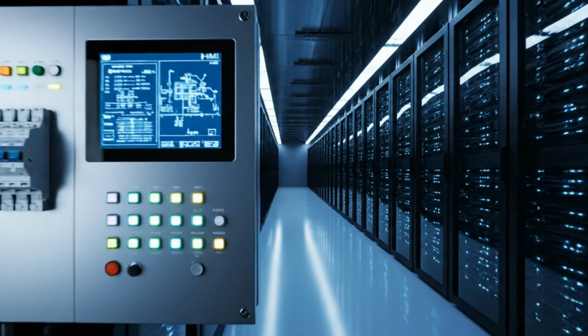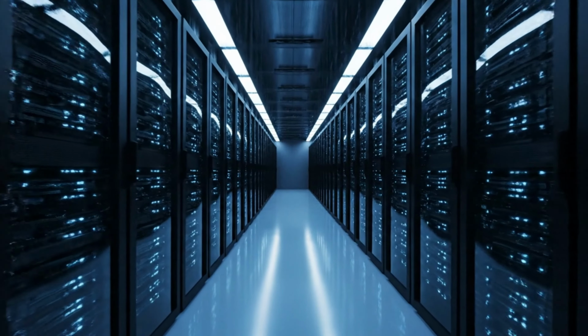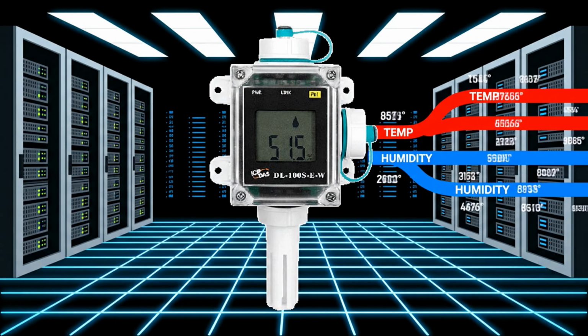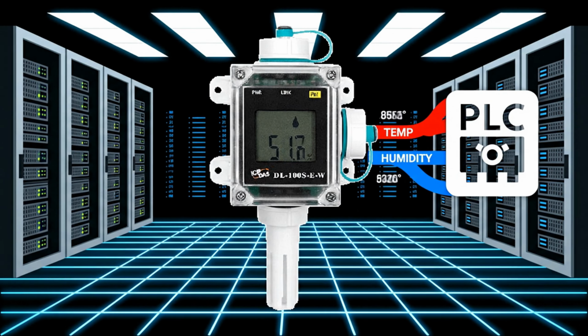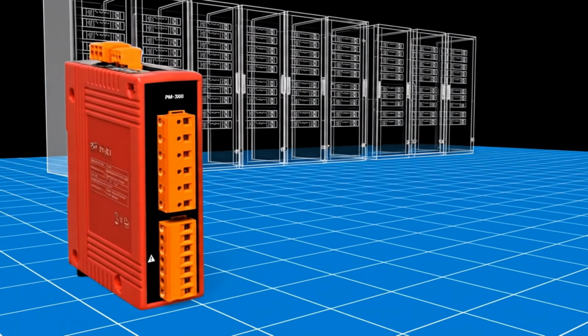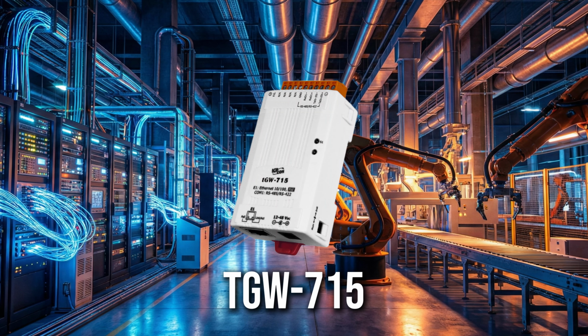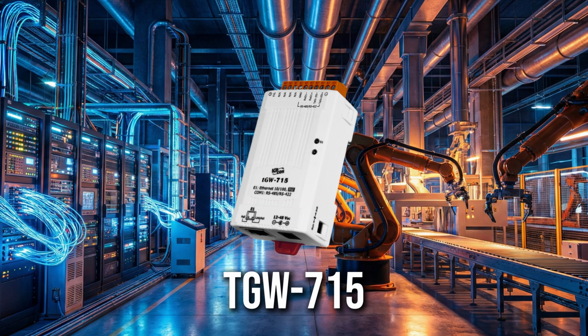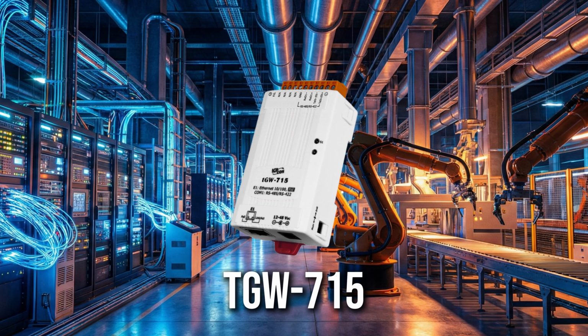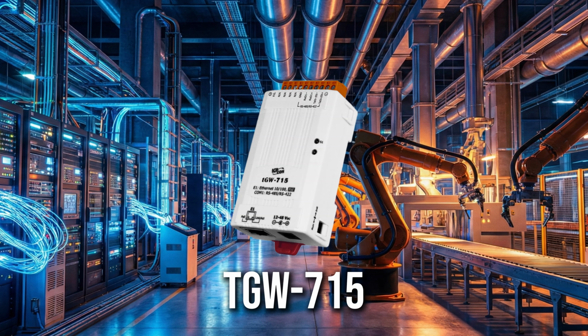And in data centers, PLCs are increasingly becoming part of the core infrastructure. They work alongside environmental sensing modules like the DL series, which track temperature and humidity. They're paired with power quality devices such as the PM3000 series power meters to monitor circuit behavior, load conditions, and energy usage. And they often depend on gateway devices like the TGW Modbus TCP/RTU converters. These are used to bridge legacy Modbus RTU equipment into modern Ethernet-based PLC networks using Modbus TCP. Together, these devices give the PLC immediate visibility into cooling performance, energy consumption, and environmental conditions, all essential for maintaining uptime.